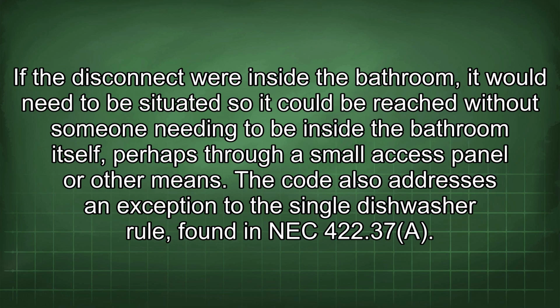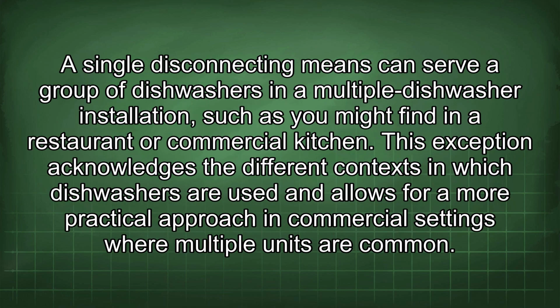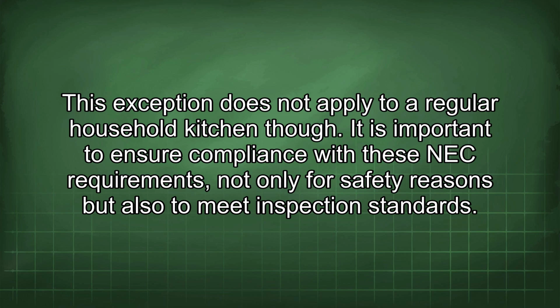The code also addresses an exception to the single dishwasher rule found in NEC 422.37a. A single disconnecting means can serve a group of dishwashers in a multiple dishwasher installation, such as you might find in a restaurant or commercial kitchen. This exception acknowledges the different contexts in which dishwashers are used and allows for a more practical approach in commercial settings where multiple units are common. This exception does not apply to a regular household kitchen though.